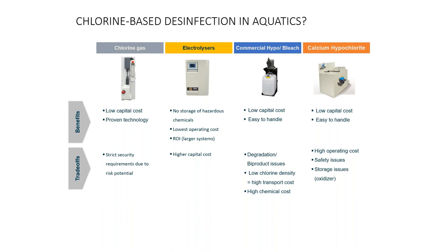An end user may need some sort of approval from the environment department to store high concentration chemicals on site. For instance, in Singapore, in order to store a chemical which is more than 10% in concentration, operators or clients would need an approval from the National Environmental Department in Singapore. Therefore, you need to produce additional documents, and you need to have bulk containment bunds to prevent spillage of the chemicals.